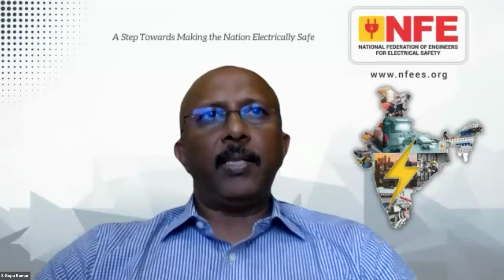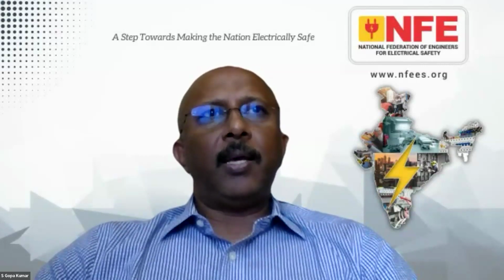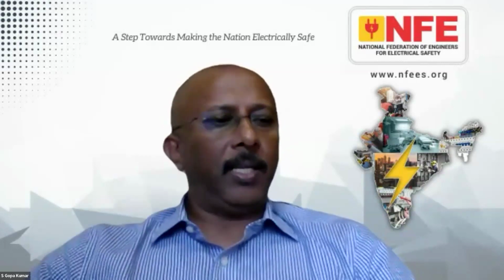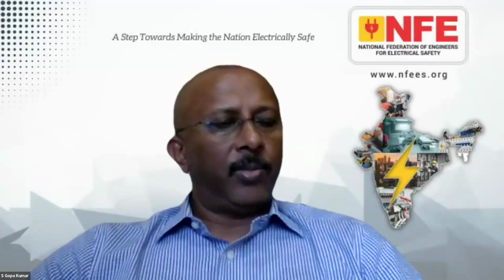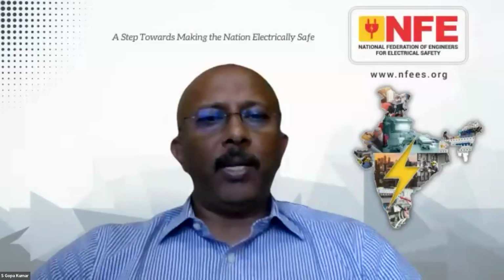Online condition. Like the loop impedance test, then the RCD functionality test. Even if you want to check the earth loop, that is also tested in the live condition itself. But when you test the RCD online, if the RCD trips, that means the entire system will trip. Correct. So we are deliberately making the RCD trip to ensure whether it is working fine or not. Then it becomes offline. Okay, understood. Actually, out of the 10 tests listed in the standard, the first 4 are in off condition. The next 6 are in on condition. That is how it is. If you look at the standard, these are actually written in the standard.